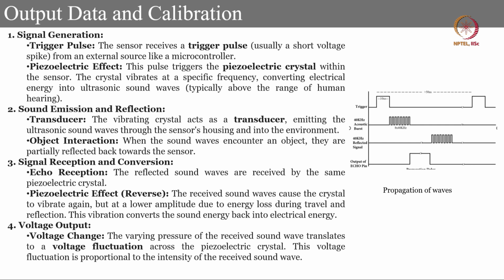Signal generation, we use a trigger pulse. The sensor receives a trigger pulse, and when it receives a trigger pulse, it will generate a burst of acoustic signals, and this acoustic signal goes and hits a target, and then this burst will come back. And when it comes back, there is an output echo pin.